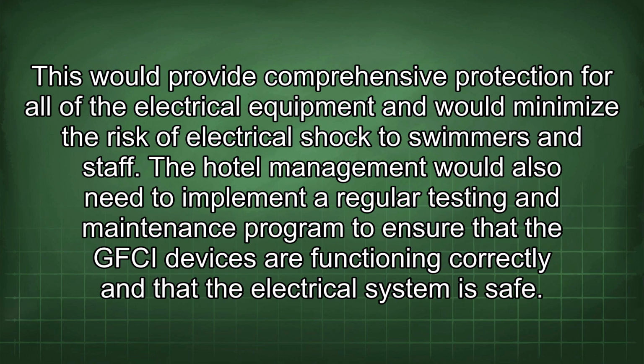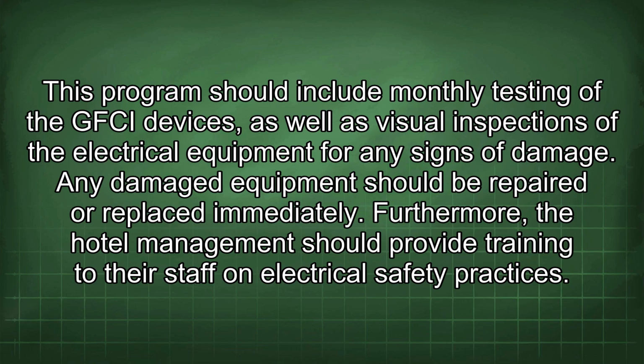The hotel management would also need to implement a regular testing and maintenance program to ensure that the GFCI devices are functioning correctly and that the electrical system is safe. This program should include monthly testing of the GFCI devices, as well as visual inspections of the electrical equipment for any signs of damage. Any damaged equipment should be repaired or replaced immediately.